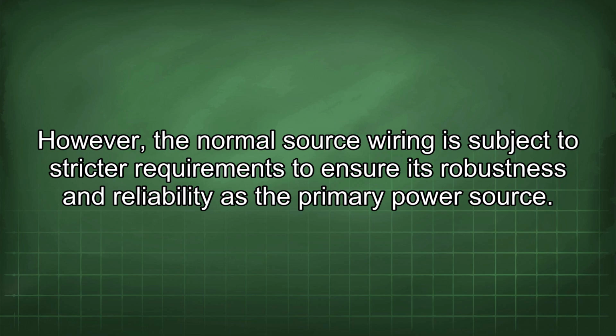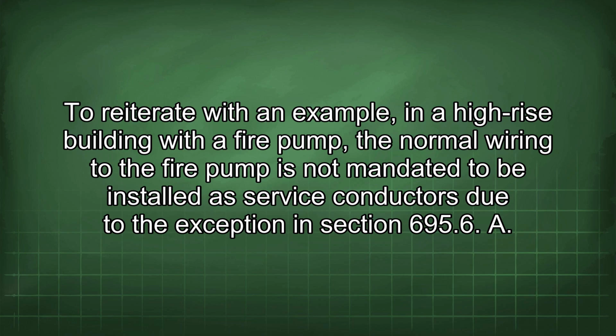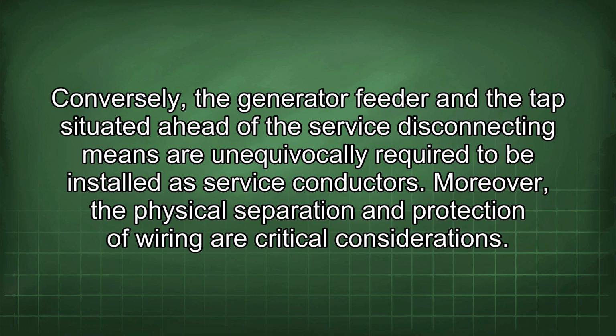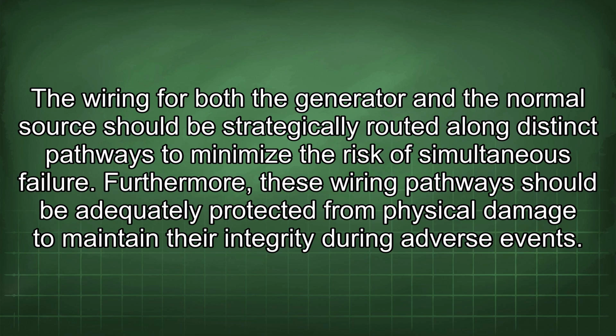To reiterate with an example, in a high-rise building with a fire pump, the normal wiring to the fire pump is not mandated to be installed as service conductors due to the exception in section 695.6. Conversely, the generator feeder and the tap situated ahead of the service disconnecting means are unequivocally required to be installed as service conductors. Moreover, the physical separation and protection of wiring are critical considerations. The wiring for both the generator and the normal source should be strategically routed along distinct pathways to minimize the risk of simultaneous failure. Furthermore, these wiring pathways should be adequately protected from physical damage to maintain their integrity during adverse events.